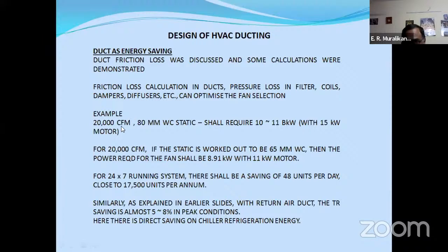We discussed a 20,000 CFM fan with 10 to 11 BKW and a 15 kilowatt motor. But if the fan had been worked out with 65 mm, then BKW is 8.9 kilowatt only. So instead of putting a 15 kilowatt motor, we can put an 11 kilowatt motor. What we do is, we don't do a proper exercise about the fan static selection. Somebody says 50 mm, another will say in that project I put 80 mm, so put 80 mm. And we blindly put 80 mm. But the actual recommendation, 65 is okay for us. But we put 80 mm.